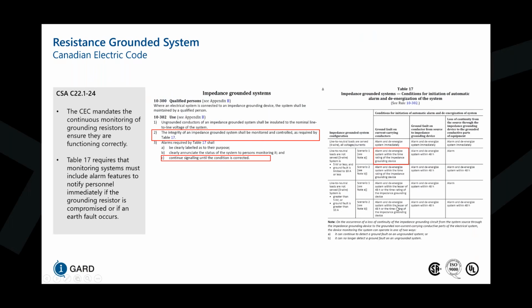But if I look at the circulating wattage on these systems that are greater than 5 kV versus a low voltage system, it may be hard to hold the fault for 48 hours. So for example, if I have a 600 volt system with a 10 amp NGR, my circulating wattage is about 3,470 watts. So that's just taking the line to neutral voltage of the system and multiplying by 10 amps. Now, in a 13.8 kV system with a 10 amp NGR, that would equate to 80 kilowatts circulating for 48 hours, which is likely not possible. So most consultants and end users choose to trip with time coordination with respect to their feeders and their subfeeds, and just try and make sure that they can get the most uptime by just isolating the feeder that is experiencing the fault.